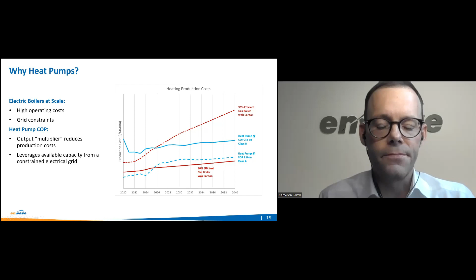So that brings us to the implementation of heat pumps with district energy systems. One application for district connected heat pumps exists for distributed local plants. Take, for example, an existing steam customer who is looking to decarbonize, who has access to district chilled water, but they don't have access to a nearby district heating water system. That customer's cooling and heating profile over the year may look like the graph on the left. In this case, the customer could consider building a standalone heat pump plant to serve their heating profile. But generally, the heat pump plant would be sized for the peak coincident cooling load available. In this application, while the total heating required for the building is represented by the area under the red curve, the standalone heat pumps are limited to producing the area shown in green.